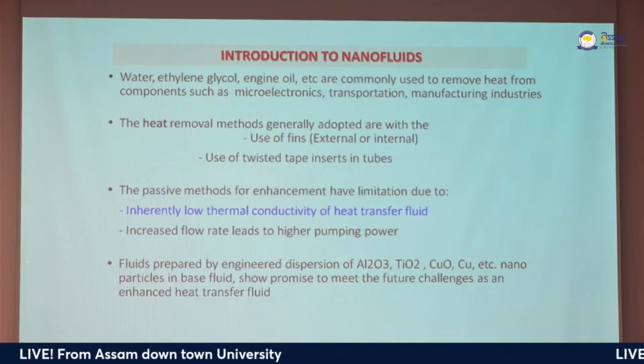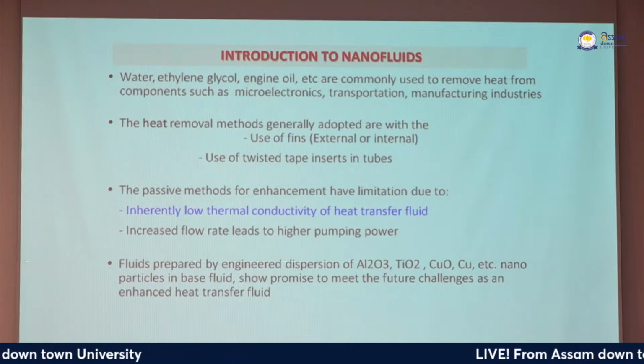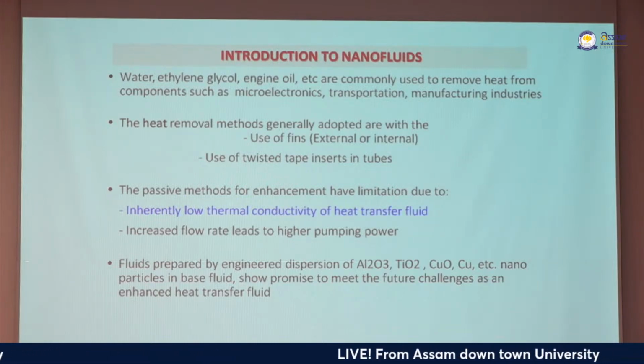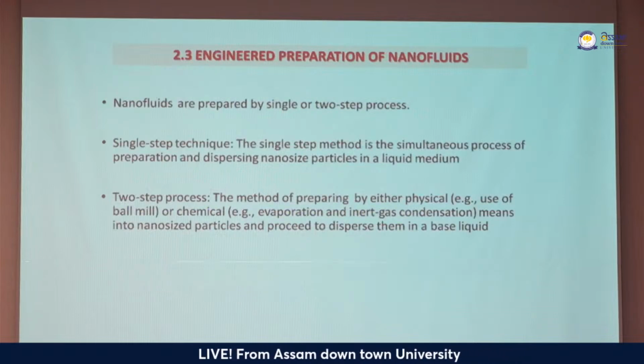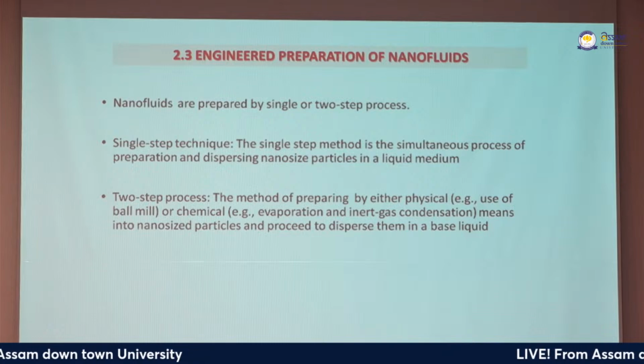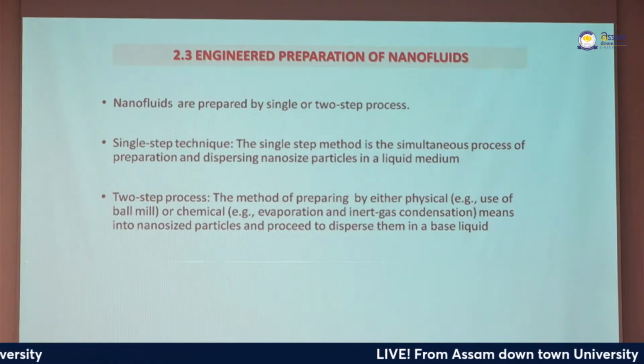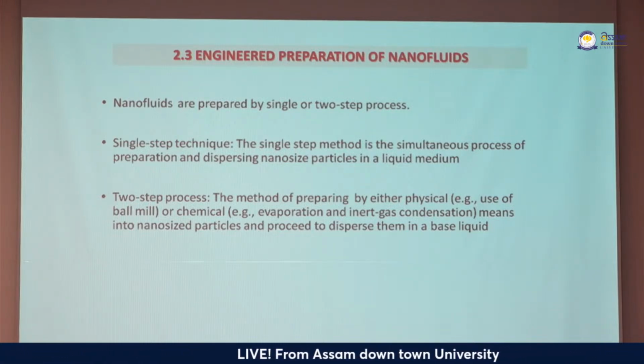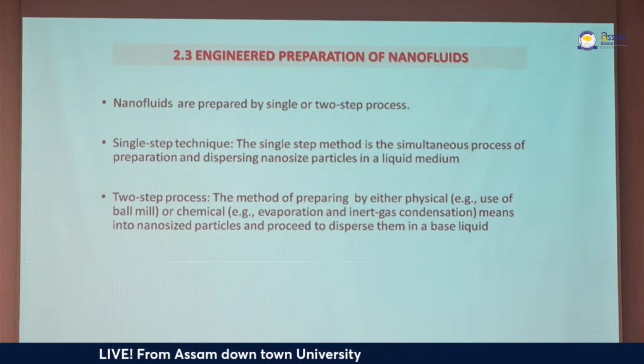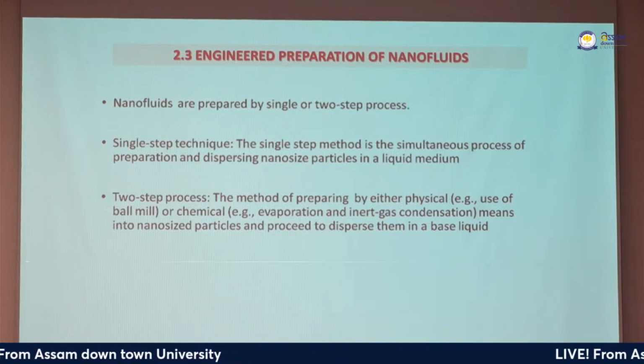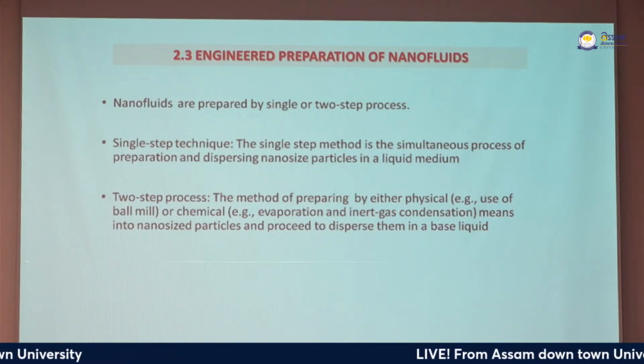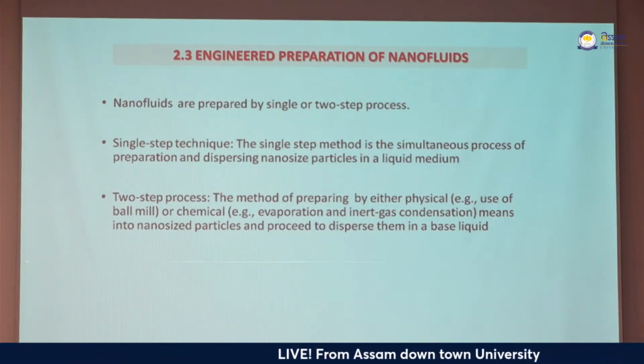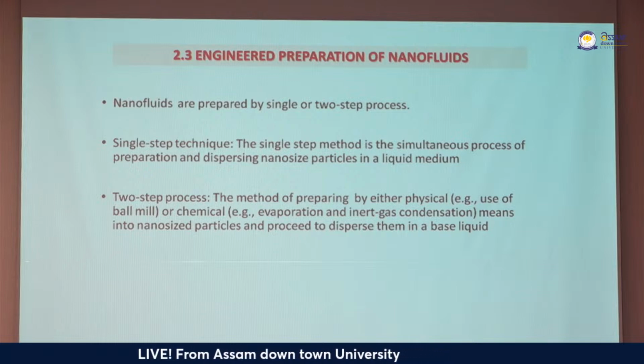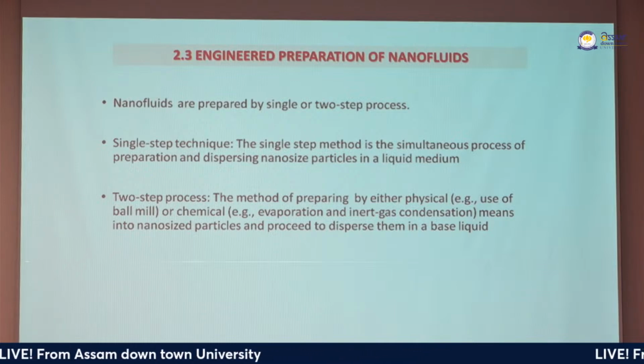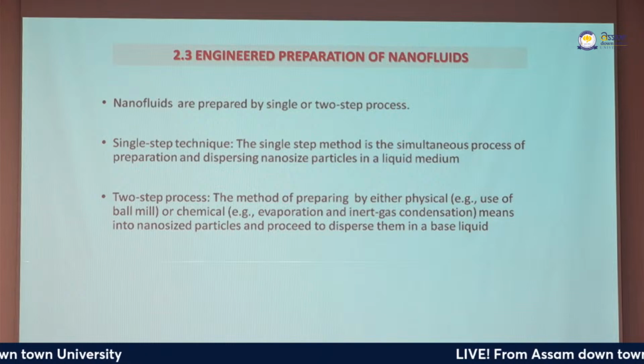So nanofluids - some of you might already be aware of what it is. Water has a thermal conductivity of about 0.6 at about 30 degrees centigrade. Its thermal conductivity, when compared to that of solids such as copper which is about 400 watts per meter degree centigrade, is quite less. So how can we enhance the properties?